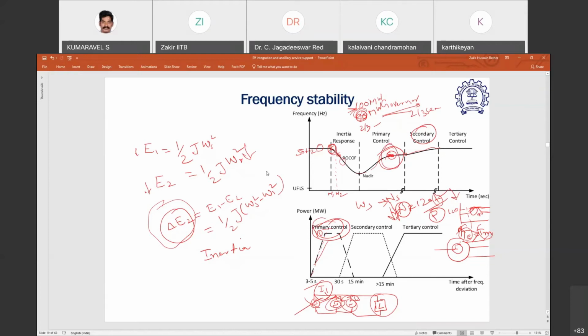So secondary control has two functions. One is it should bring frequency back to the nominal value. Second is it should release the primary control reserve, which means secondary control reserve should be more than primary control reserve. If primary control reserve is, let us say, 450 megawatt, secondary control reserve may be actually 500 megawatt, because it will release this entire 450 megawatt, and also it may need that 50 megawatt to bring frequency back to the nominal value.